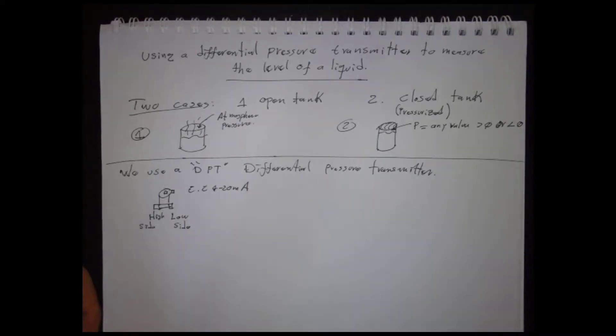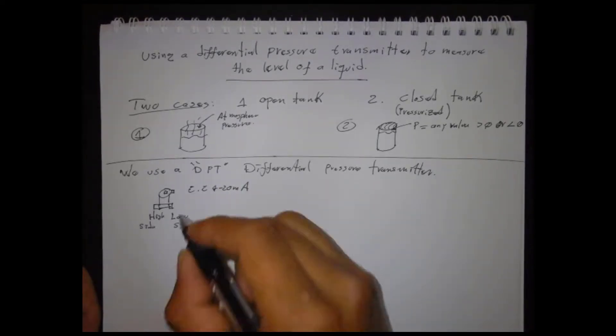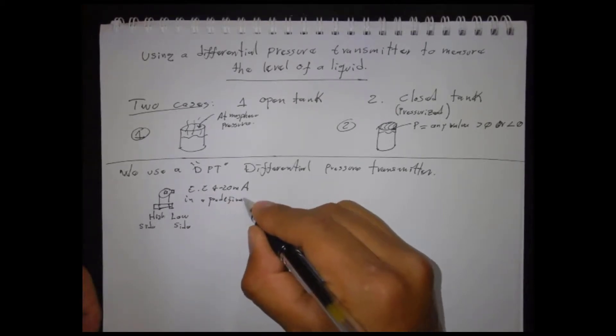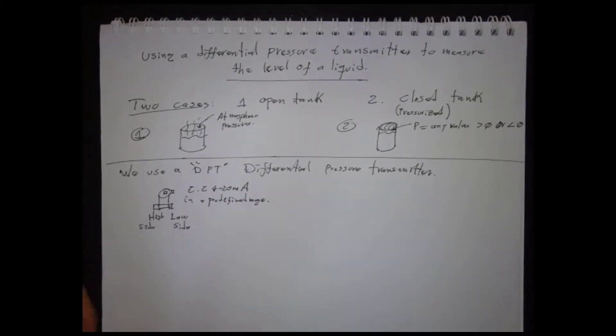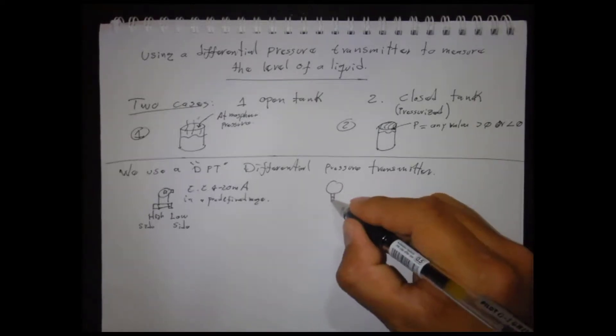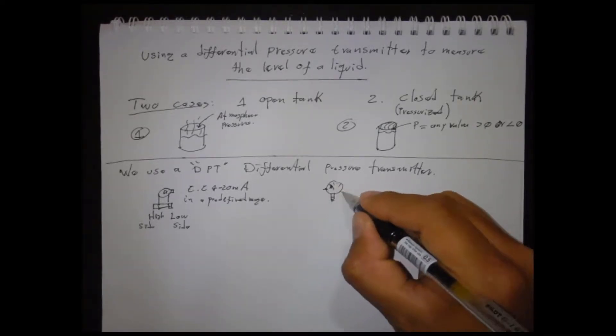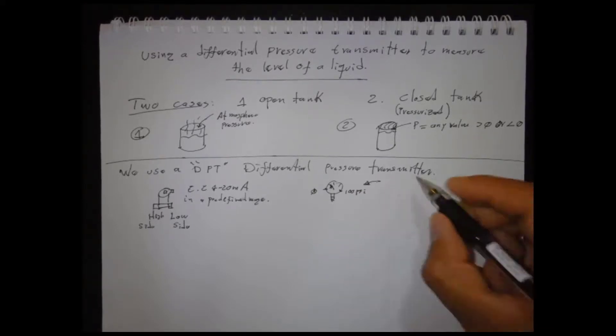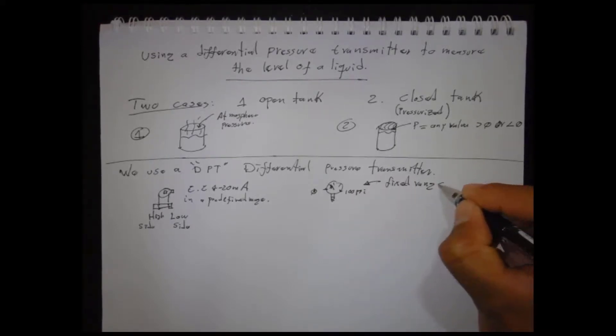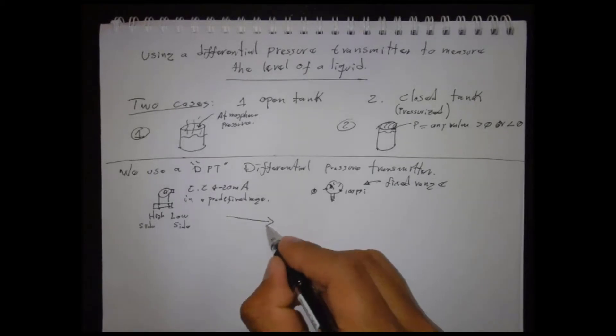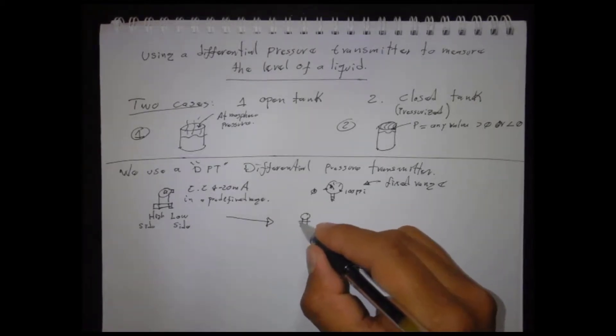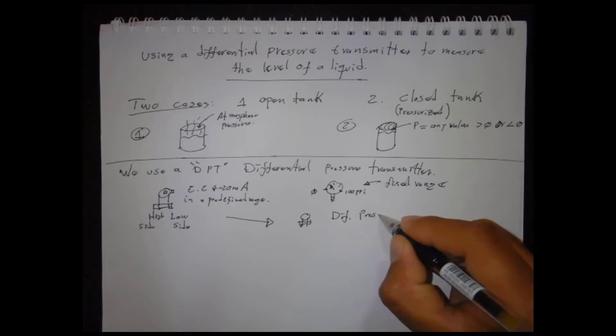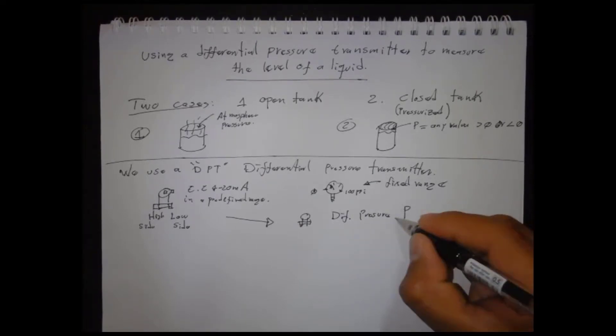For example, let's consider a manometer. A manometer has a fixed range from 0 to 100 psi and cannot be changed. A DPT takes the difference of pressure between the high and low side, and that difference could be positive, negative, or zero. In the case of the transmitter, the range can be defined by the user.